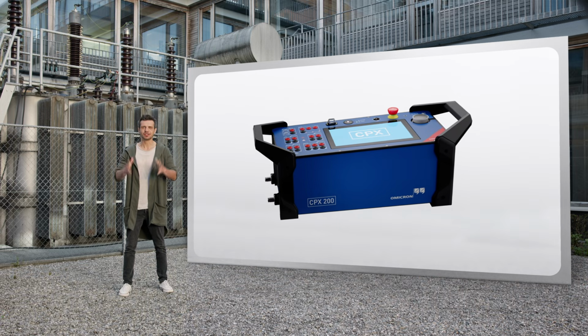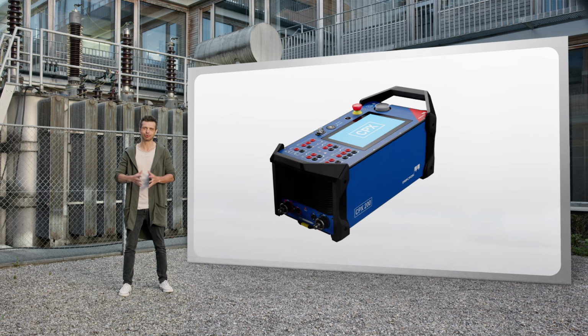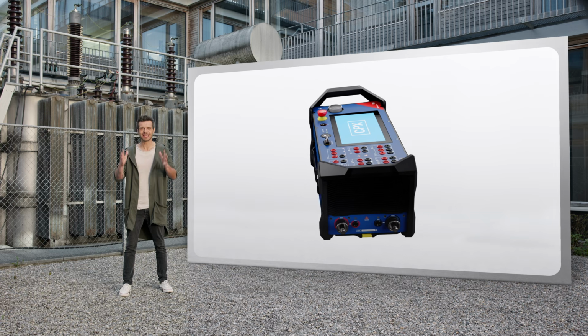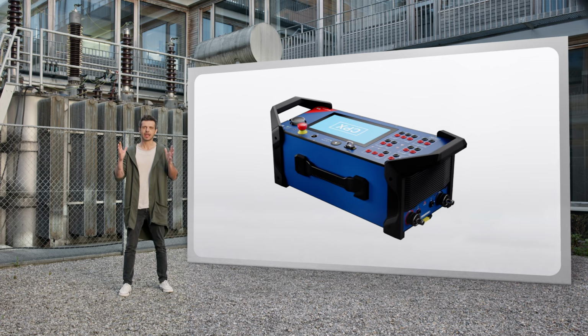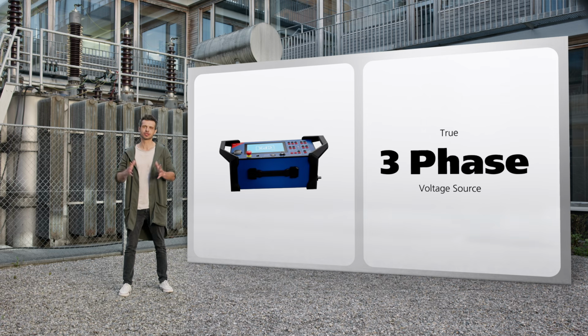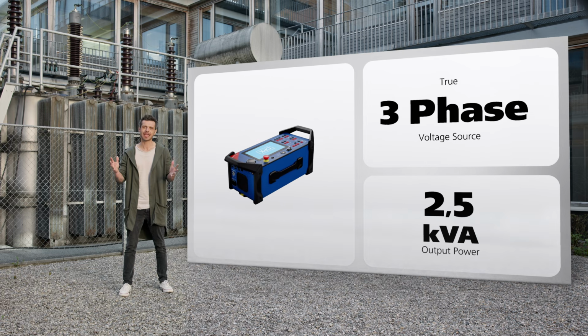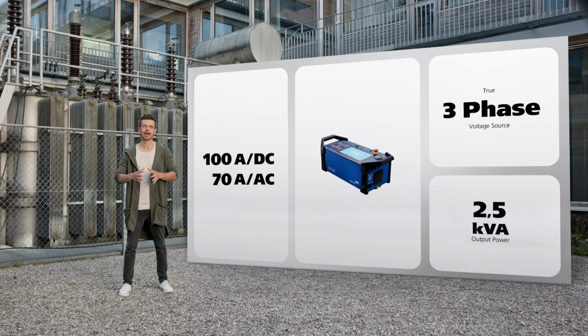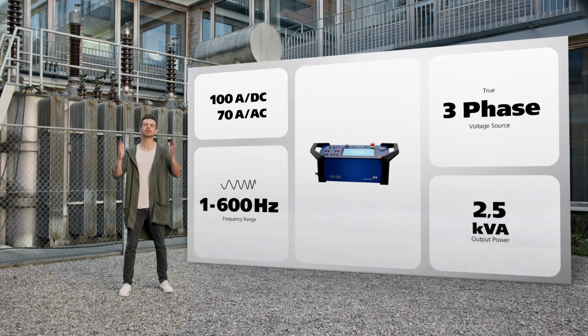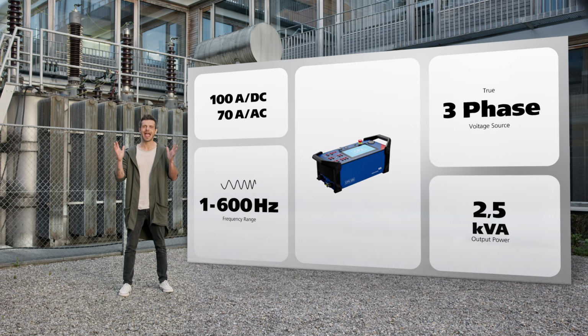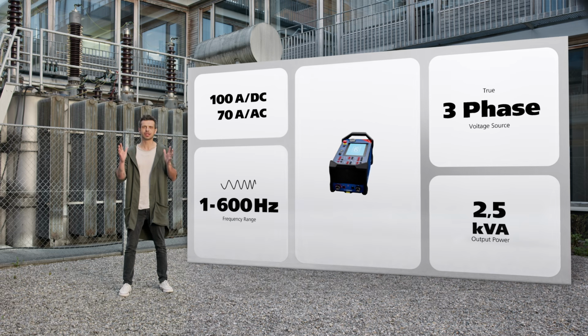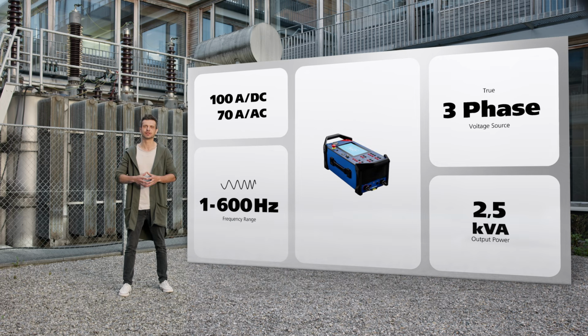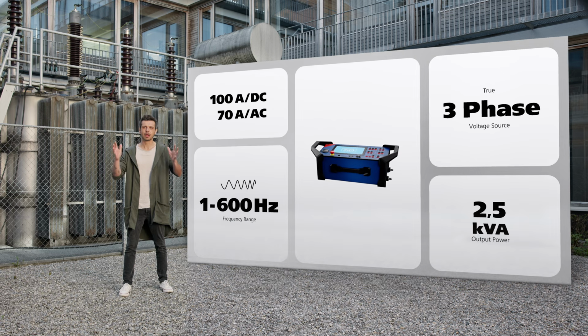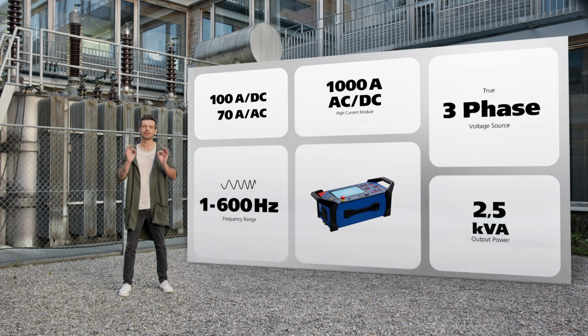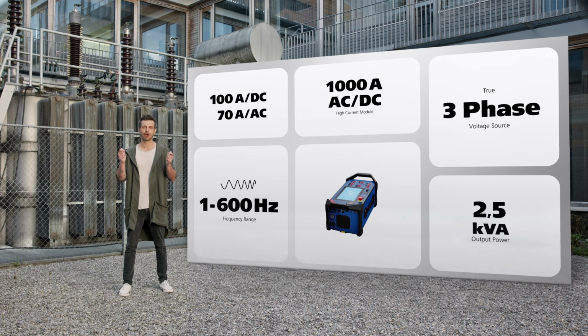The CPX 200 is not just the most versatile test system we have ever created, it is also the most powerful, taking multifunctionality to the next level. It offers a fully configurable true three-phase voltage source, a powerful 2.5 kVA output capable of delivering 100 amp DC and 70 amps AC with a high compliance voltage and a frequency range from 1 to 600 Hz. We also included an active discharge mechanism to ensure huge inductive loads are discharged in a fraction of the time you are used to. Upgrading with the optional high current module will even give you 1 kA AC or DC for high current injection testing.